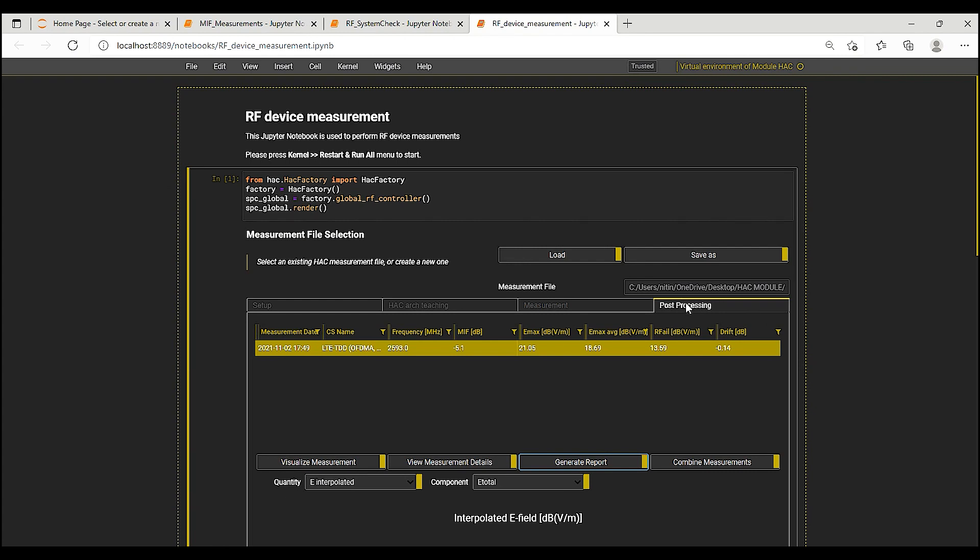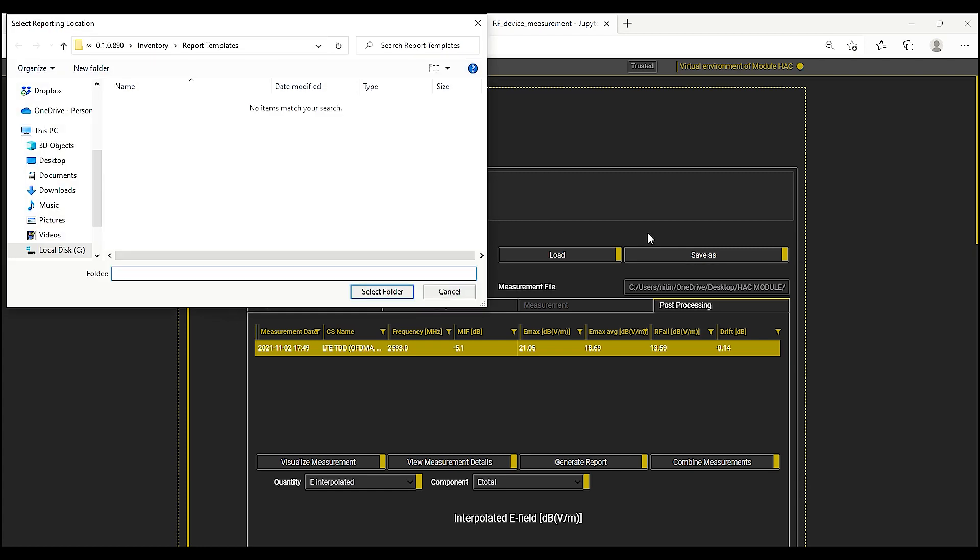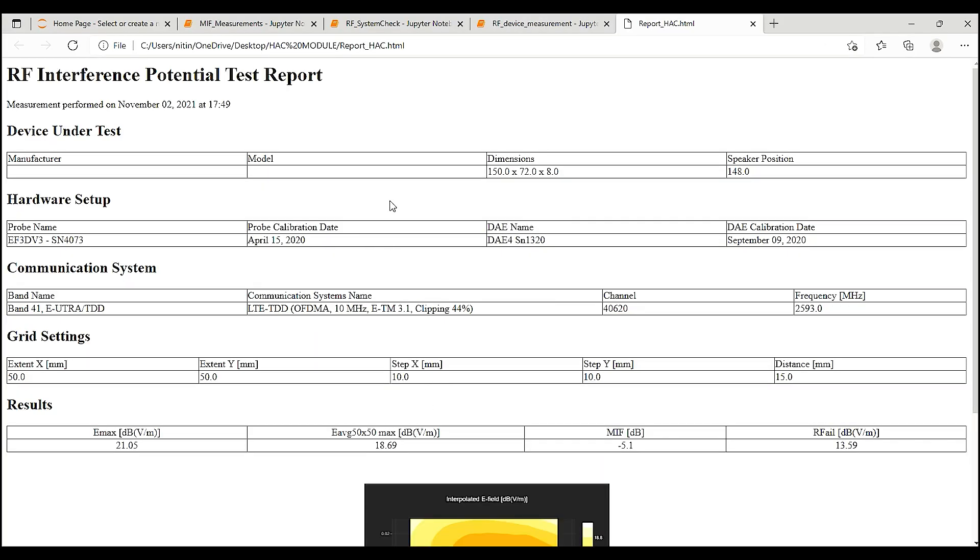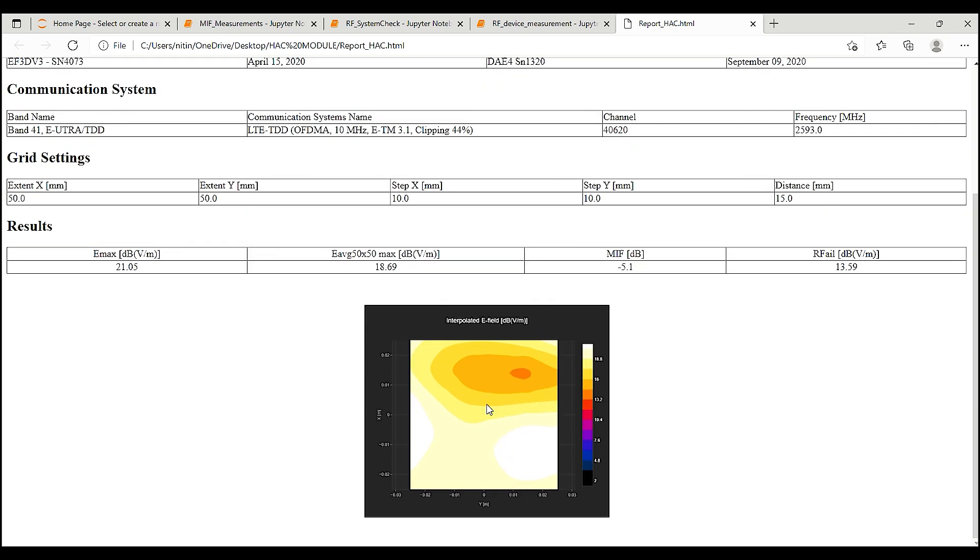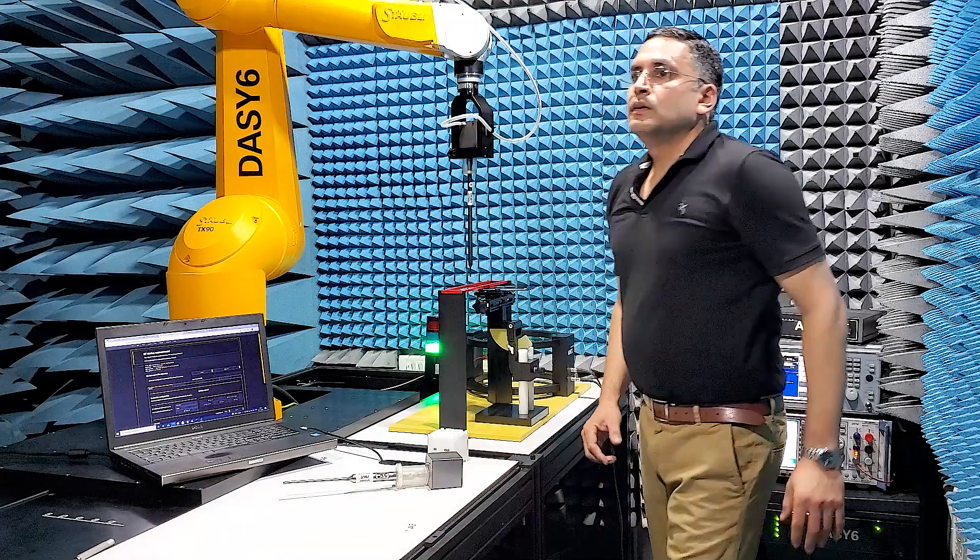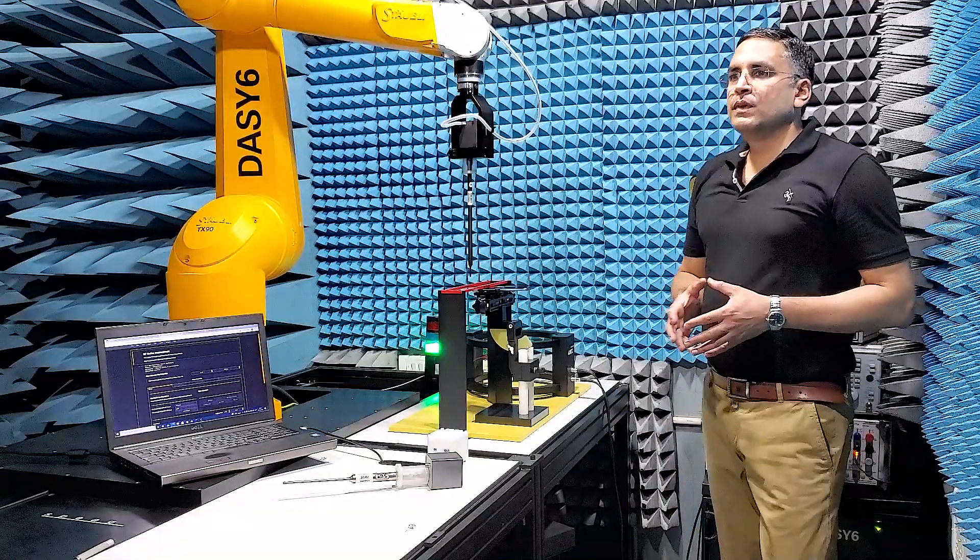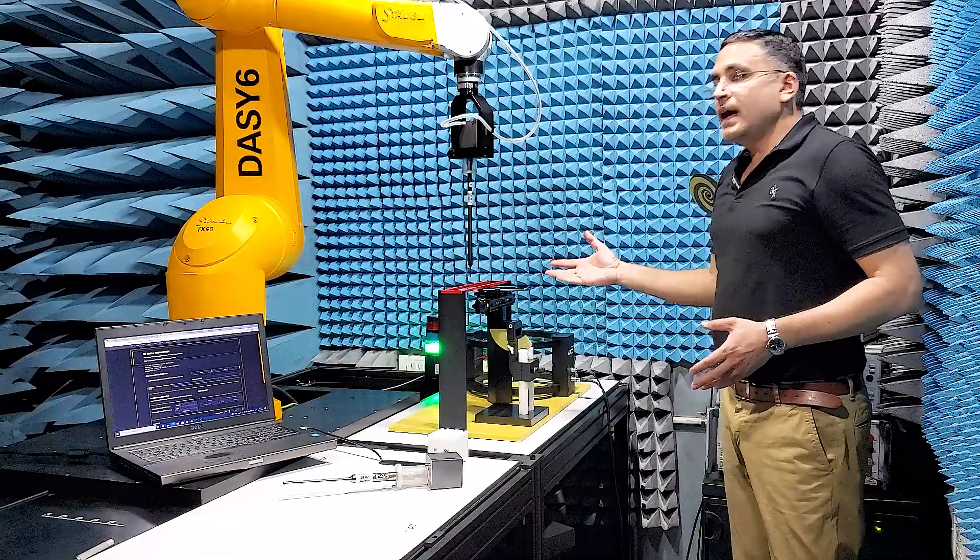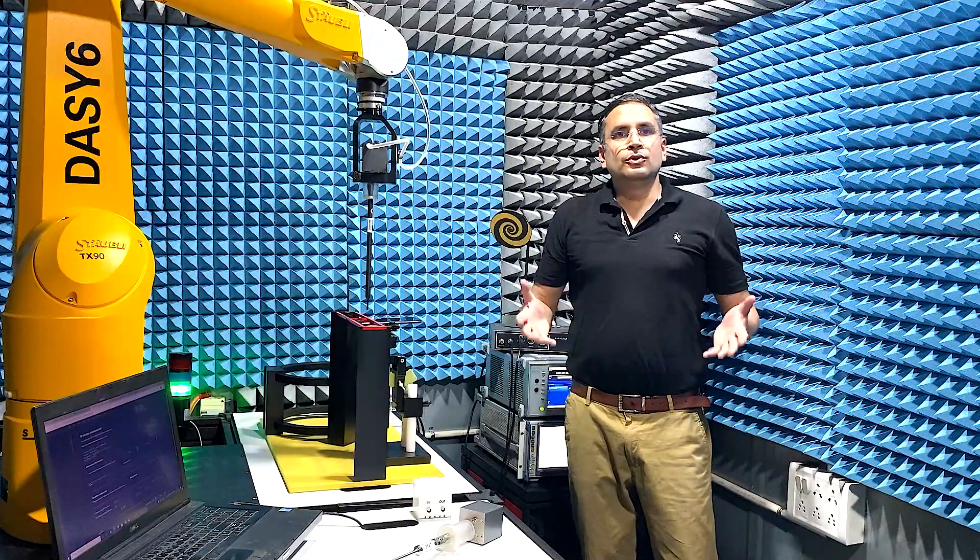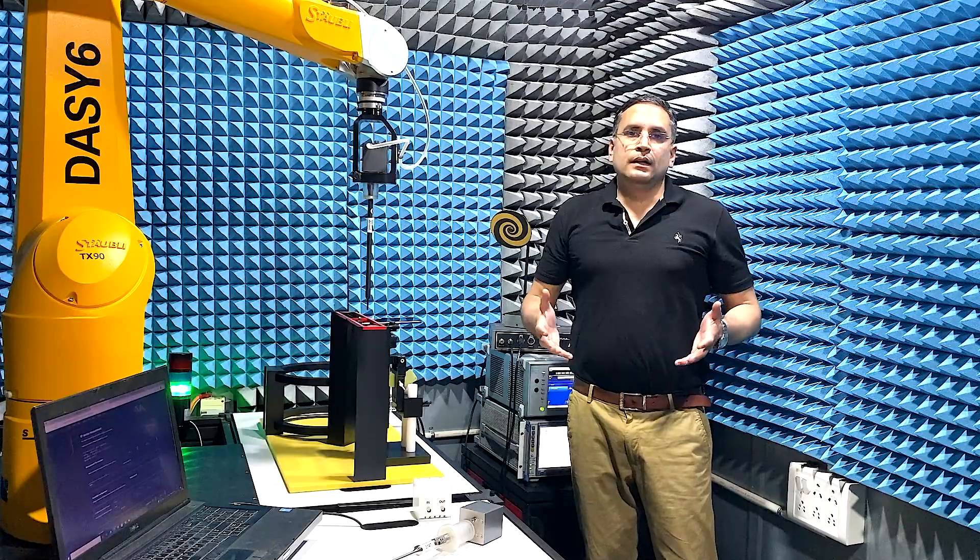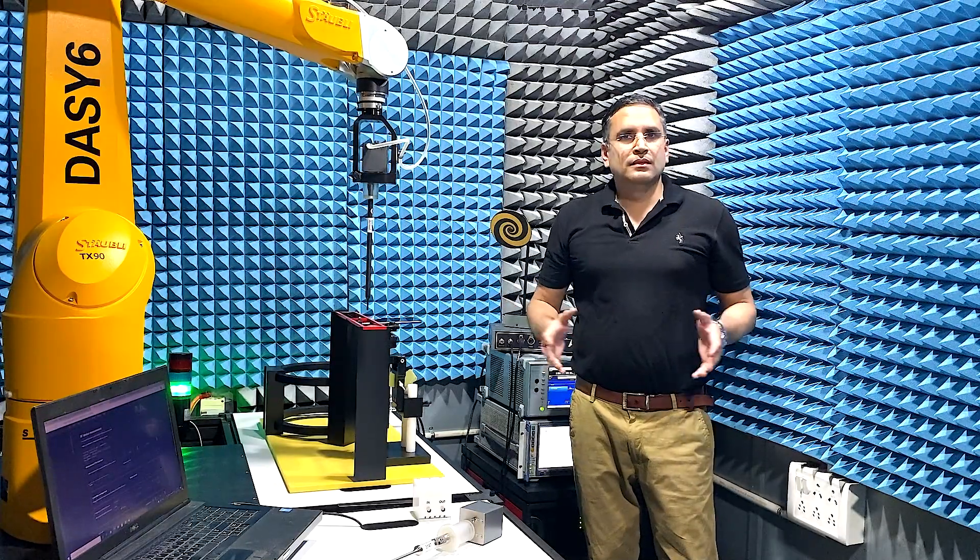Detailed test reports for any test case are available via this button here. It shows the details of the test including the grid settings, measured values and the field distribution. So, the RF emission measurements with the new HAC module are both easy to use and at the same time precise.